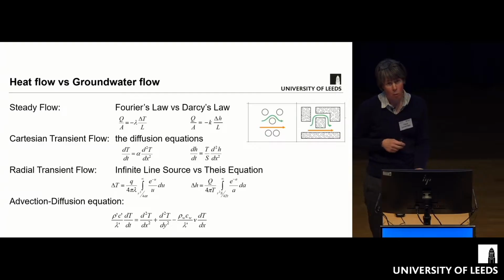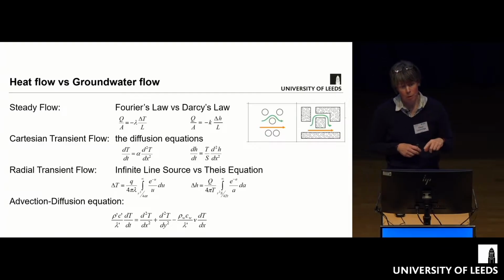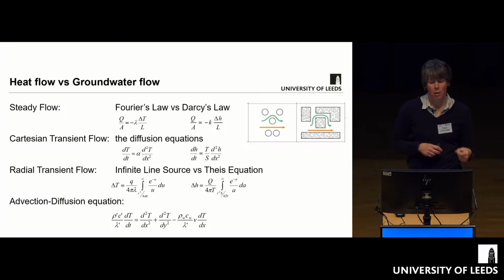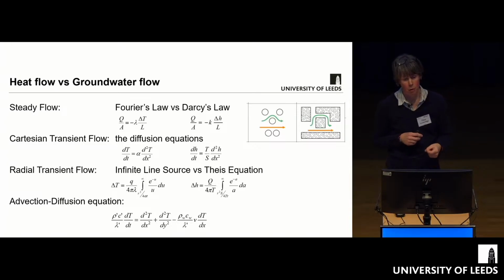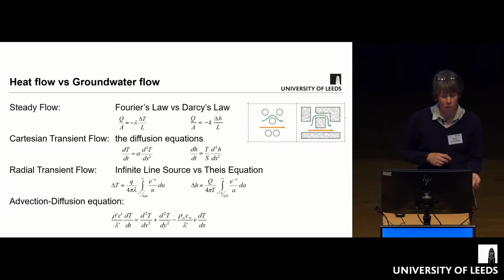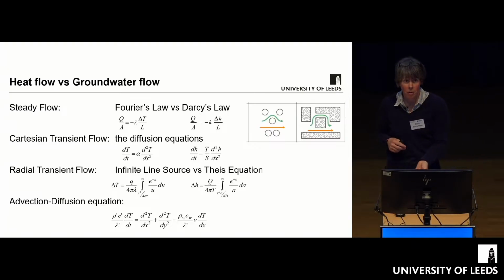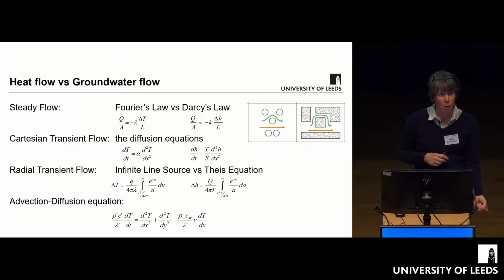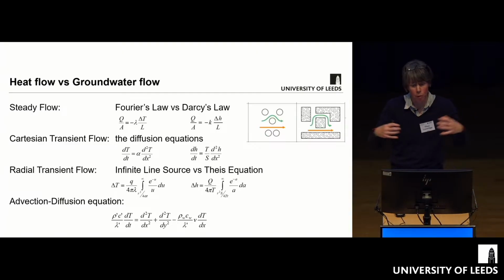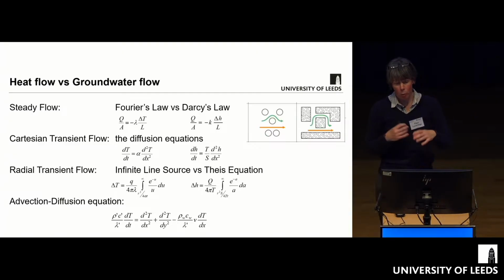We might be dealing with a three-dimensional problem, but a lot of problems in ground heat exchange for heat pump systems are simplified to one-dimensional radial transient flow. So I'll be referring a few times to the infinite line source. If there are any hydrogeologists in the room, that is a perfect analogy for the Theis equation, used to interpret groundwater pumping tests - basically radial flow into a well, and we'll come back to that again.